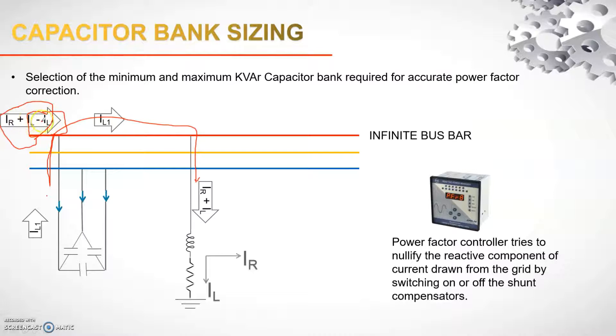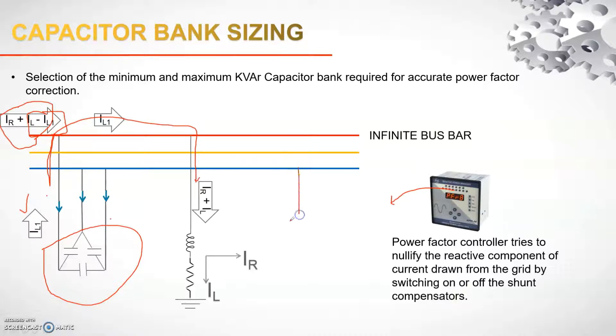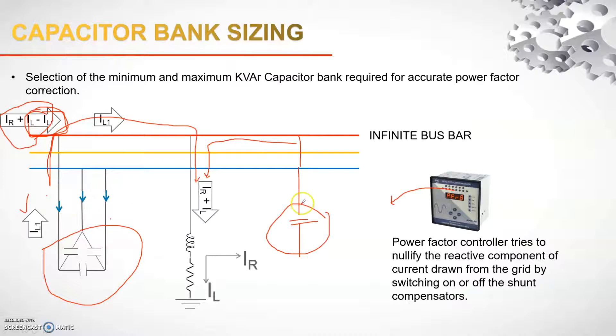To achieve 100% reactive power compensation, I want this reactive component to be zero. If one capacitor bank cannot provide the required current, the power factor manager through another channel will connect another capacitor bank. More capacitor banks will be turned on until this current value ideally equals zero.